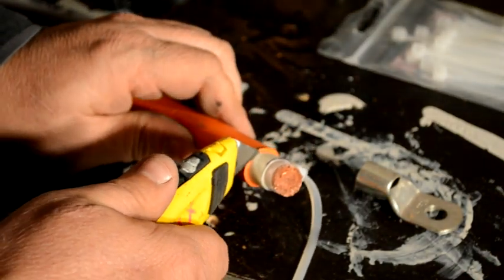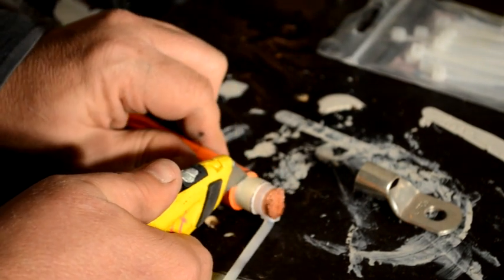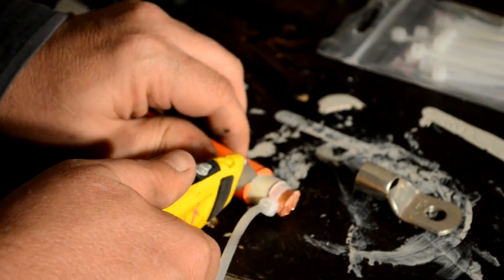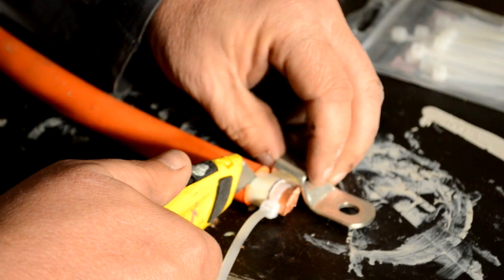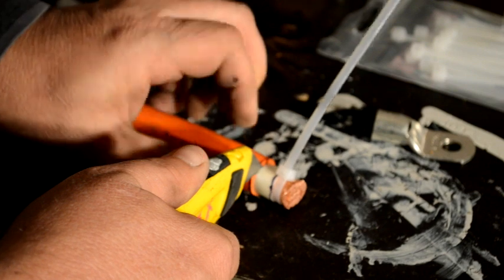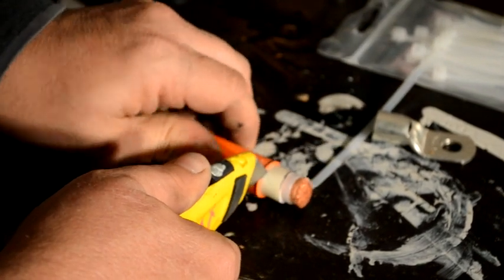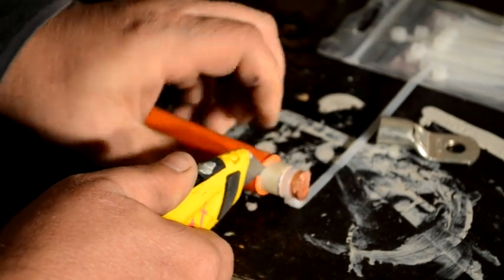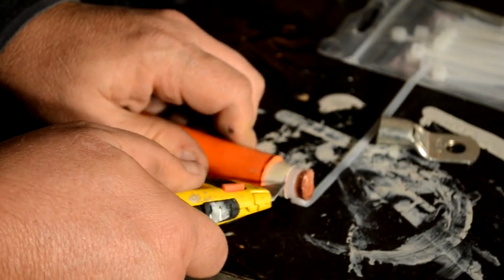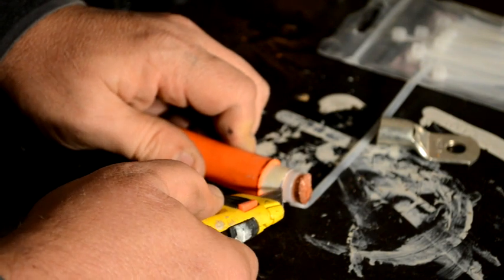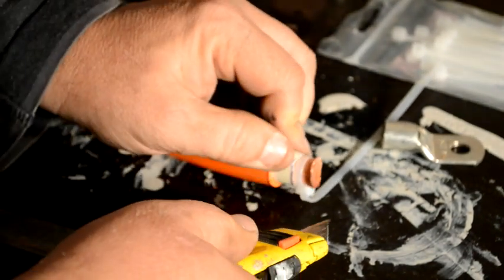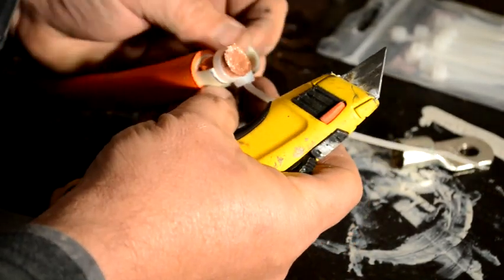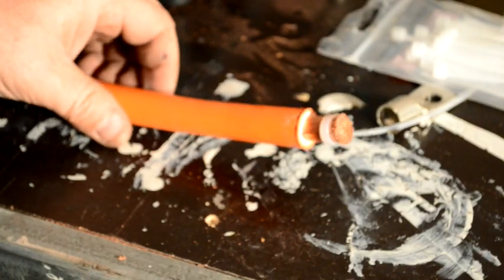Once that's done, take our knife and now cut off the remaining inner insulation, or if you've just got single insulated cable, cutting it back to the length that you require for your lug. Again being careful not to cut into the copper itself. Sometimes it's just unavoidable, things happen, you might pick up one or two strands, and that's fine. There we go, so you'll end up with something that looks like that.